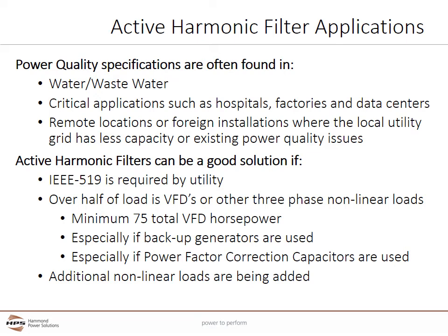Active harmonic filters can be used if over half of the load is VFDs or other three-phase nonlinear loads. If VFDs are involved, generally a minimum of 75 total VFD horsepower is needed before you would start to consider an active harmonic filter. Active harmonic filters can decrease the size of backup generators and help protect power factor correction capacitors from being damaged by harmonic currents. Consider active harmonic filters if additional nonlinear loads are being added that could stress the current power system.